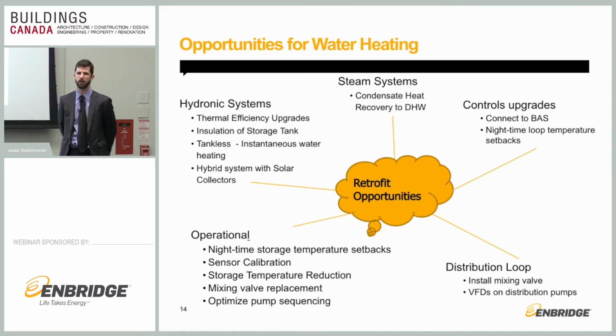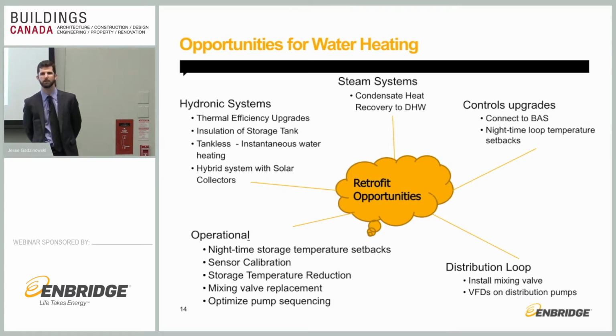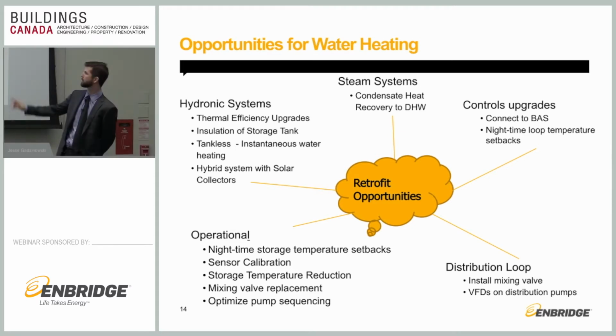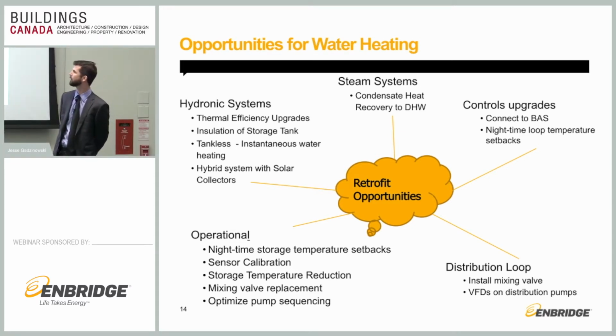You don't need a storage tank. You just put in the instantaneous heater, seeing that more and more. Or even some of the more proactive people are doing hybrid solar collectors for domestic hot water and offsetting gas that way. It's a more expensive approach, and the paybacks are incredibly long, but we see that out there. For steam systems, like I said before, a lot of condensate heat recovery to domestic hot water. It's a good opportunity.